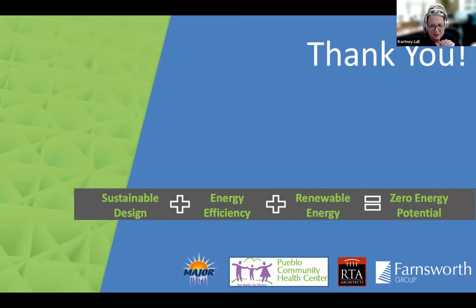Great. Another question is, which energy model tool was the team using in the design process to accurately model the energy reduction impact of the geothermal exchange system? I use Carrier's HAP program, but I've done it in Trace, or you can do it in eQuest. The important thing is to understand your loads and to understand that Carrier, Trane, and those guys sell HVAC equipment, and to properly size your cooling side of things, because they can be super conservative on the cooling and a little less conservative on the heating side of things. So understanding realistic load balance is extremely important. But yeah, I use Carrier HAP on that.